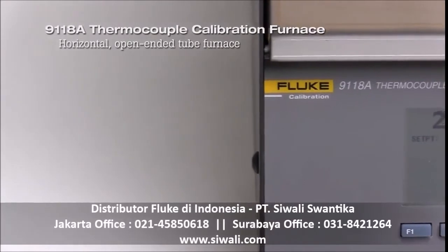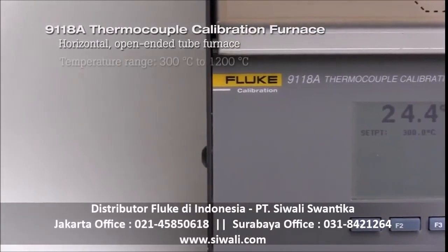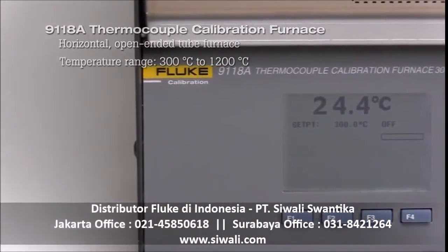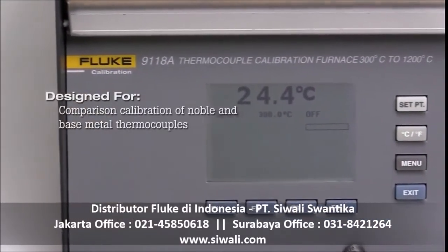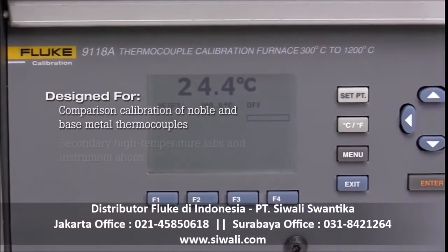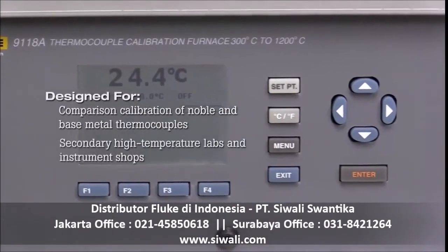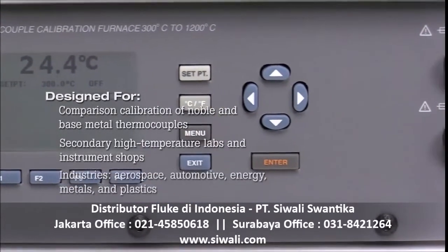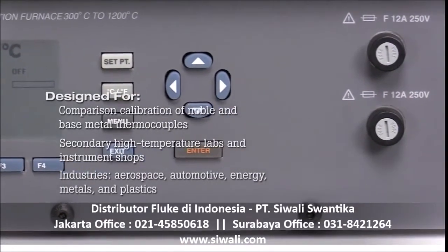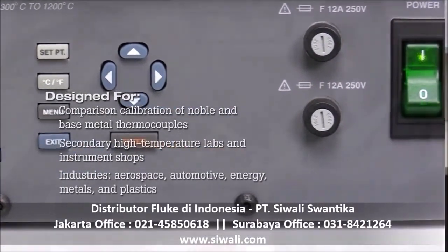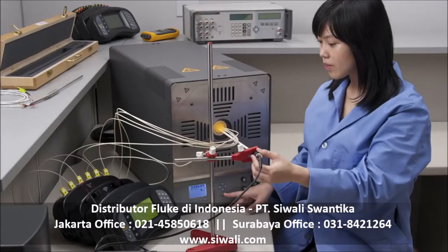9118A Thermocouple Calibration Furnace is a horizontal, open-ended tube furnace with a temperature range of 300 to 1200 degrees Celsius. It is used for comparison calibration of noble and base metal thermocouples by secondary high-temperature labs and instrument shops in industries such as aerospace, automotive, energy, metals, and plastics. Calibration tolerances for these applications are typically 1 degree Celsius or better.